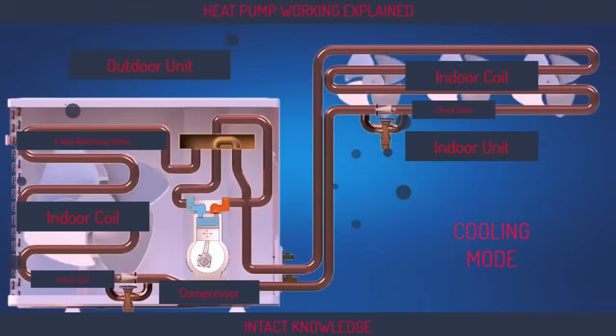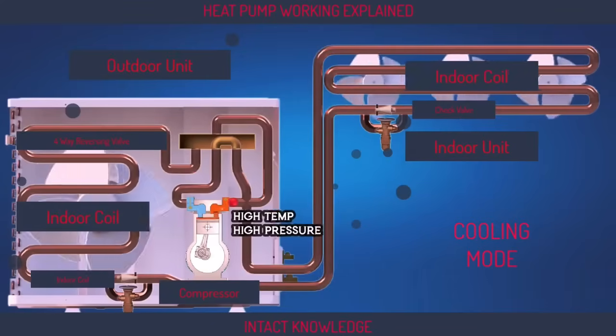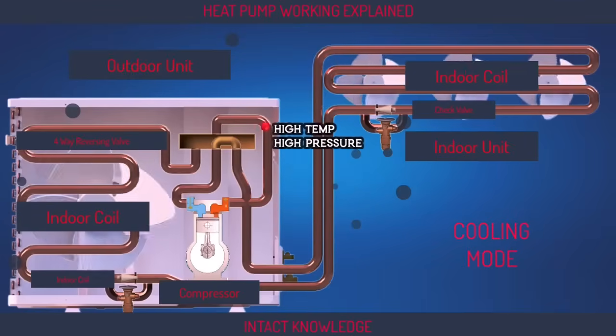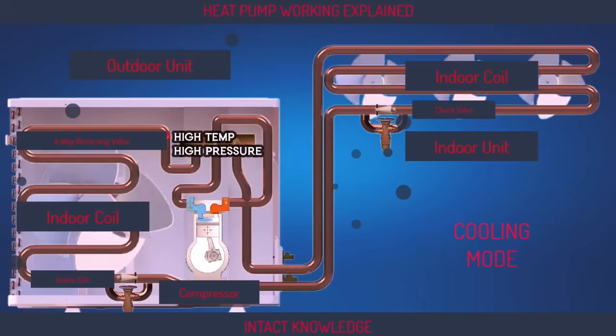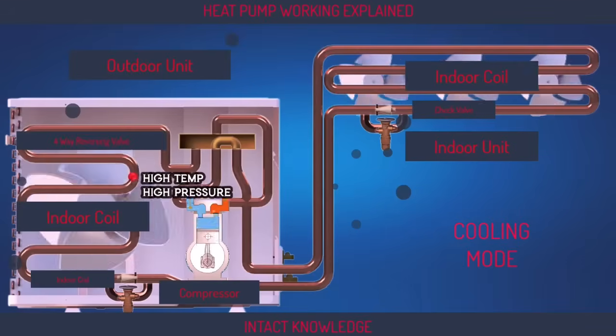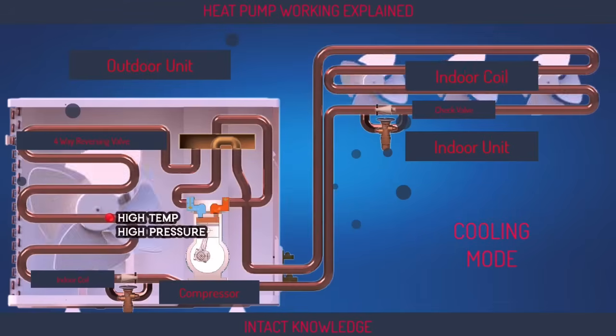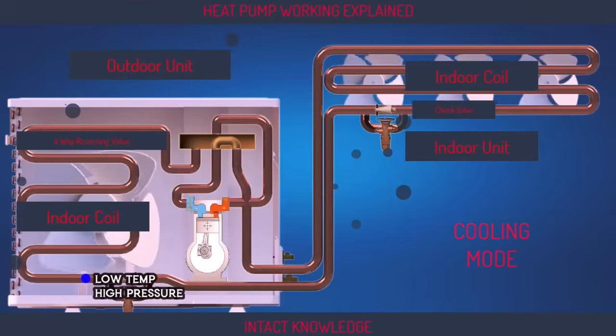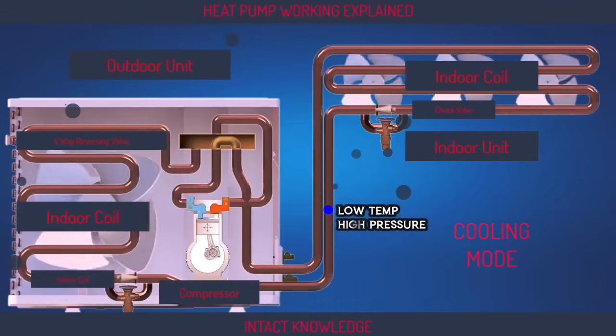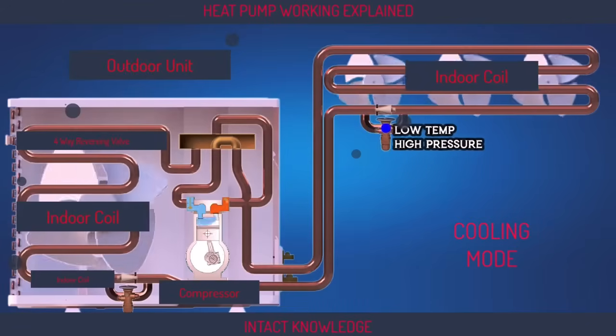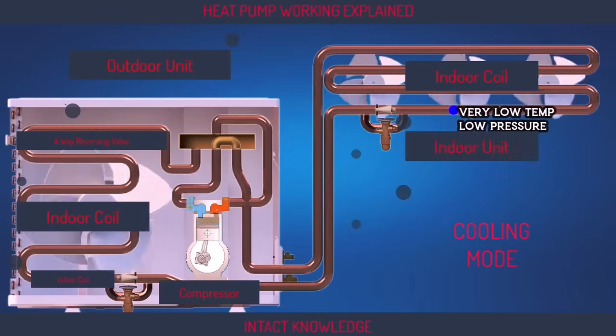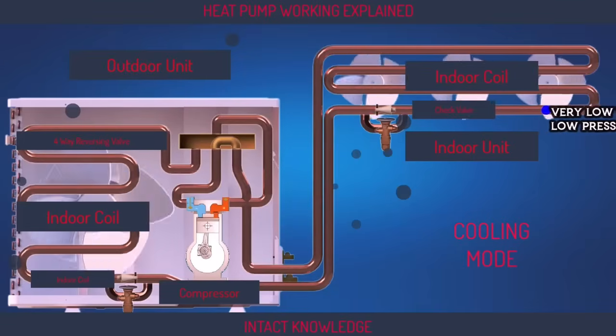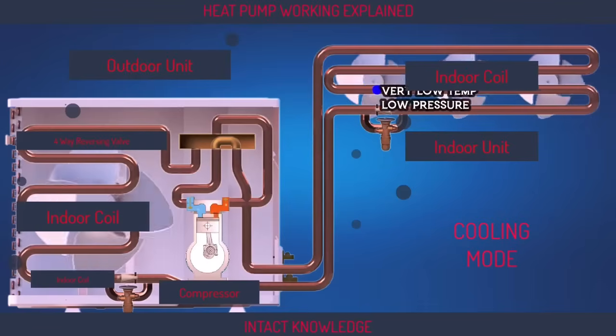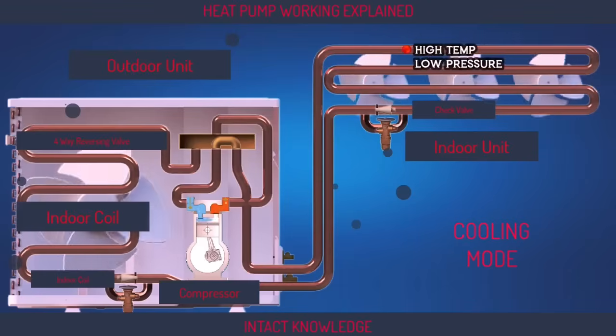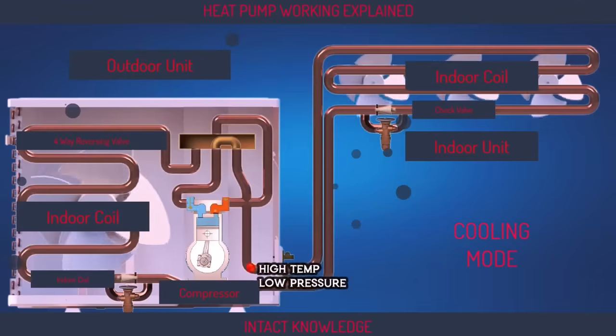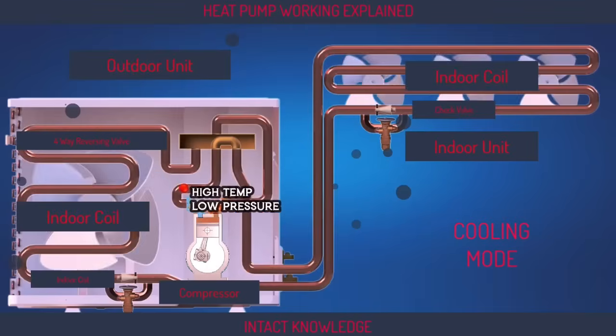Cooling mode. First, let's see how the system works in cooling mode. The refrigerant at high temperature exits the compressor and enters the reversing valve. From there, it flows to the outdoor unit. In the outdoor unit, the refrigerant cools down and travels through the non-return valve to the indoor unit. And then it passes through the expansion valve. When the refrigerant passes through the expansion valve, its temperature drops significantly, providing a cooling effect as it reaches the indoor coil. The indoor fan motor then blows this cool air into the room. As the refrigerant absorbs heat from the room, its temperature rises and it returns to the compressor, completing the cycle. This process continues in a loop, allowing the heat pump to function in cooling mode.